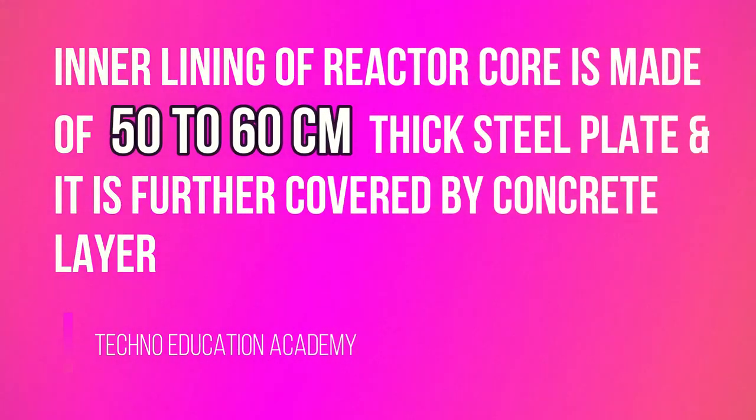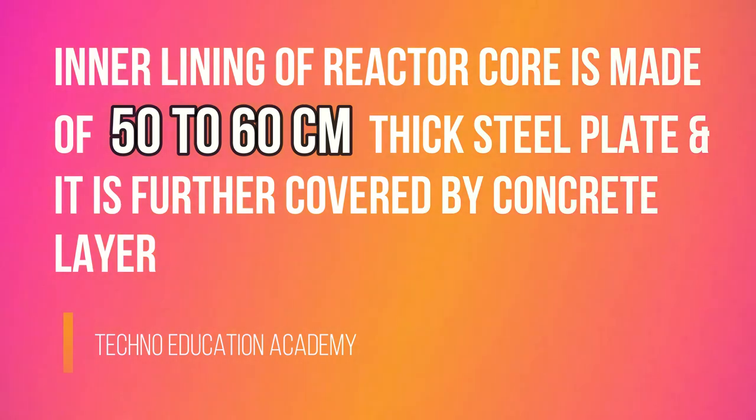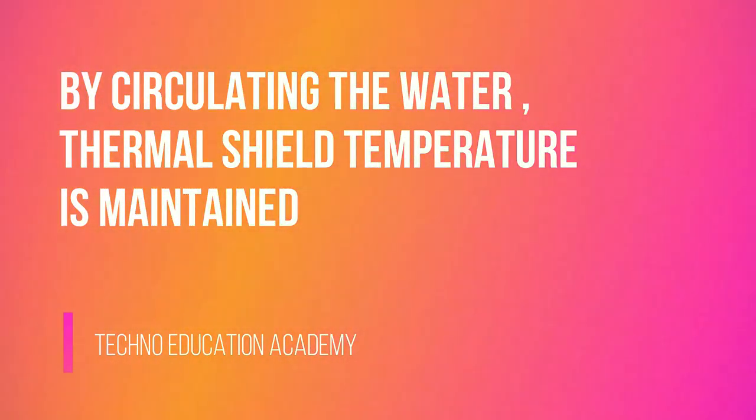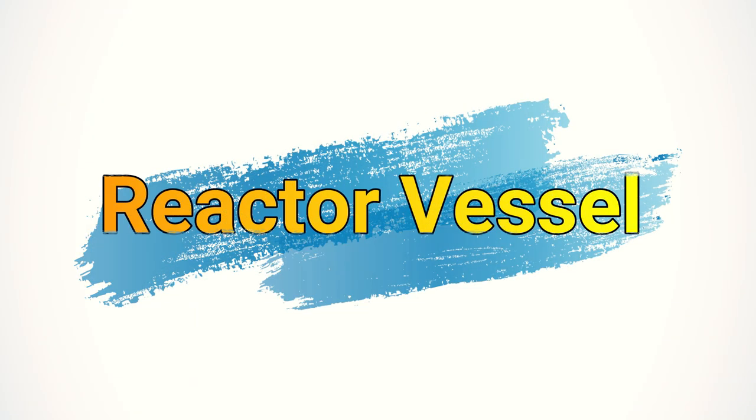Neutrons, gamma rays, and all other radiations are effectively absorbed by concrete and steel. The inner lining of the reactor core is made of 50 to 60 centimeter thick steel plate and is further covered by concrete layer. By circulating water, the thermal shield temperature is maintained.